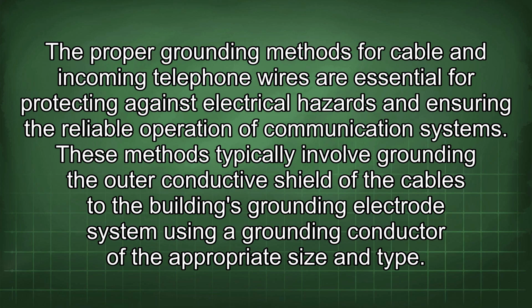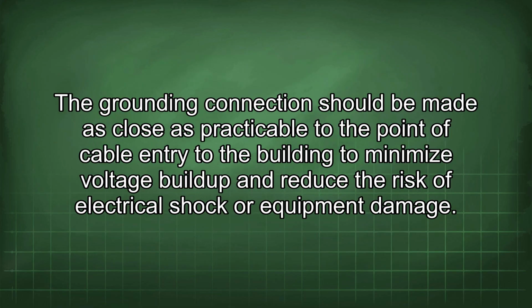These methods typically involve grounding the outer conductive shield of the cables to the building's grounding electrode system using a grounding conductor of the appropriate size and type. The grounding connection should be made as close as practicable to the point of cable entry to the building to minimize voltage buildup and reduce the risk of electrical shock or equipment damage.